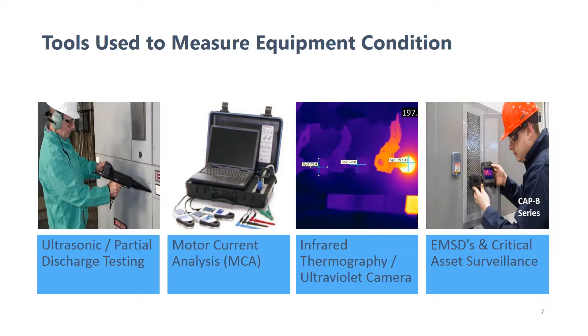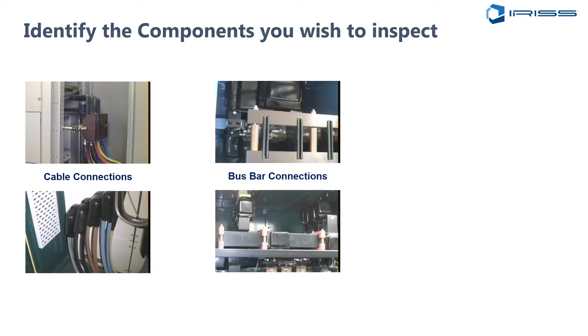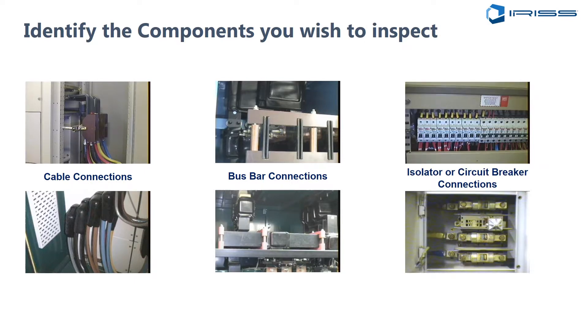When we look at electrical distribution infrastructure specifically, traditional electrical inspections commonly only look at the bolted connections within the switchgear, as these are generally considered the weakest points or most likely to fail. These may include cable connections — crimped lugs, screw and saddle clamp, booted connections, and cable to bus bar connections — bus bar connections such as splices, shipping splits, and transition sections, as well as isolators, disconnects, or circuit breakers. It's important to scan both the connection and the device itself, as internal components can overheat if defective. There may also be other hidden problems that are less obvious.